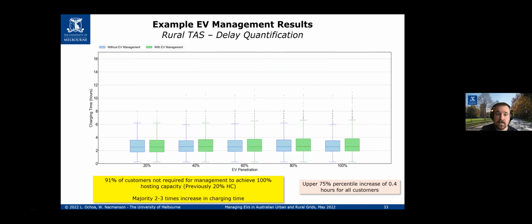The impact to customers is of course quite important. This is a different feeder now, rural Tasmania. Blue is the charging time without management, green is with management—so we're accounting for delays to some customers from managing their EVs, but we don't manage all customer EVs since we don't need to solve the issue for everyone. For 100% EV penetration on this feeder, which was previously limited to 20%, we could go from 20% to 100% by managing just 9% of customers. For lower penetrations that figure is lower, but to get every house with every EV, under 10% of customers on this feeder need to be actively managed.